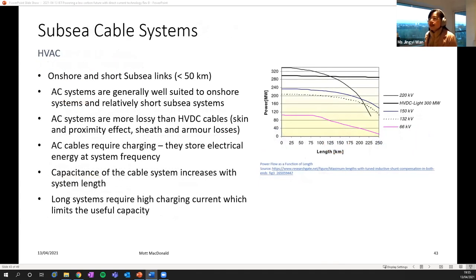Okay, next one. So now I would like to talk a bit more about the cable system in a bigger picture. As HV cable systems get longer and longer, there is a limit to how far an AC cable system can connect the power to the grid. Due to the capacitive charging current within the cable system, the longer the cable system, the larger the capacitance. And for more capacitance, a bigger conductor is needed. And we would reach a point when it becomes uneconomical or impossible to get sufficient power through the cable anymore.